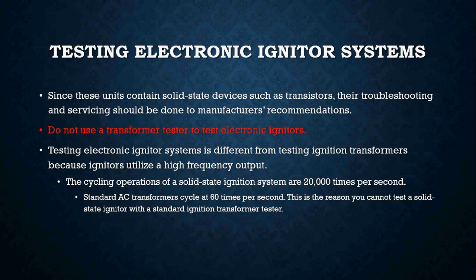So testing electronic igniter systems is different from testing ignition transformers because igniters utilize a high frequency output. The cycling operation of a solid-state ignition system is about 20,000 times per second. A standard AC transformer operates at 60 times per second. So this is the main reason why we cannot test a solid-state igniter with a standard ignition transformer tester. They just operate at a different cycling or a different wavelength.